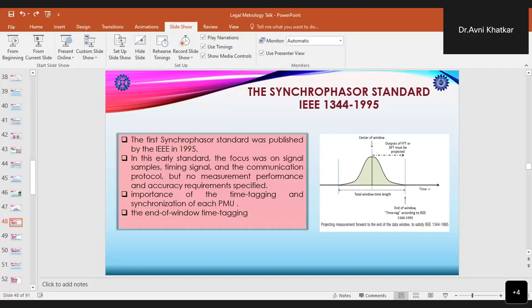And this end of window time tagging brings a lot of problems. The projection process made the measurements much more susceptible to sampling noise and any imperfect power quality. Also, quite different results were perceived from different brands of PMUs, or even some identical PMUs, which were not showing the same results because they were using different algorithms or different window lengths or different window shapes maybe during their dynamic events. So such problems were associated with this standard.